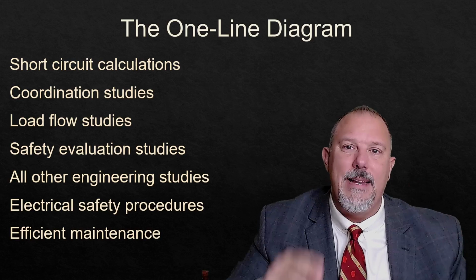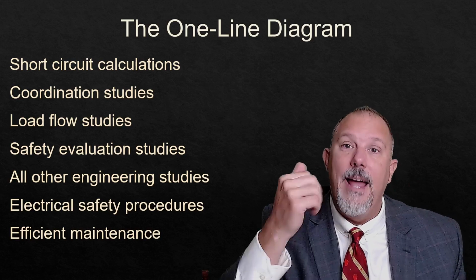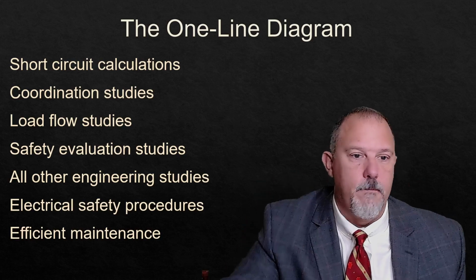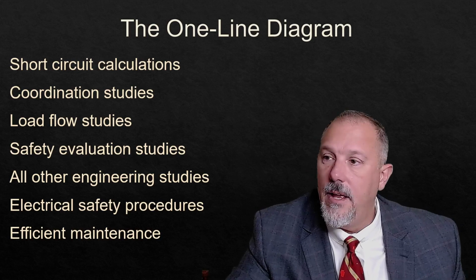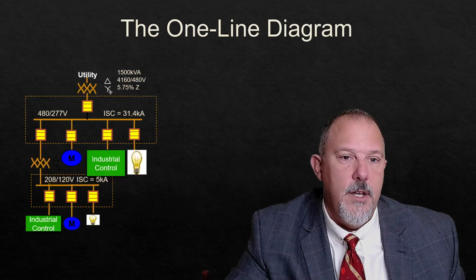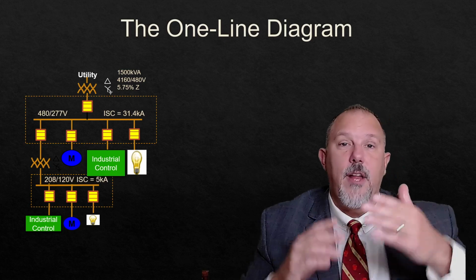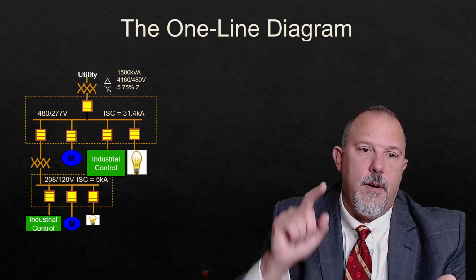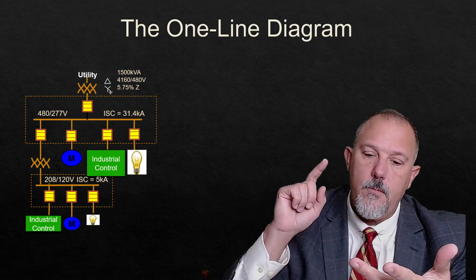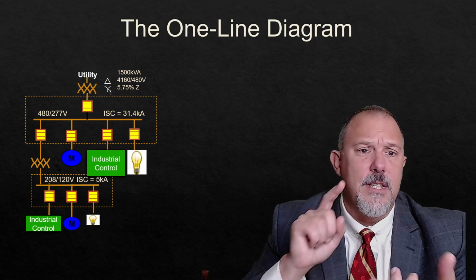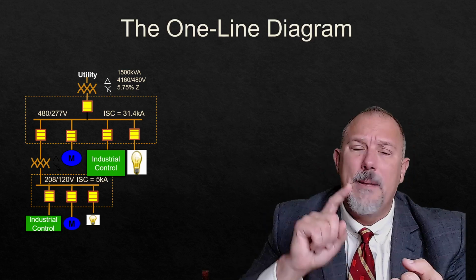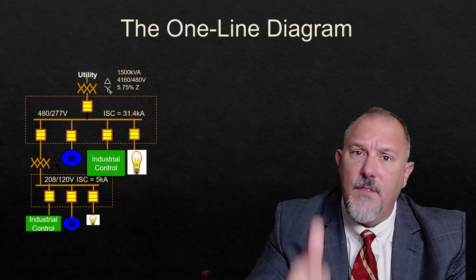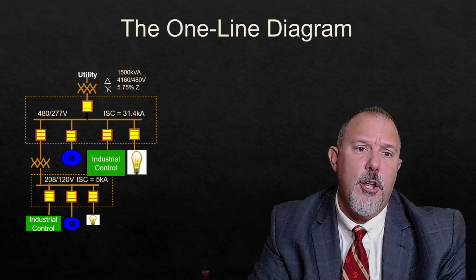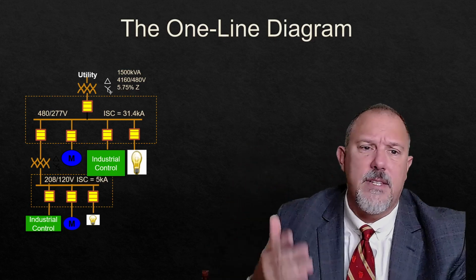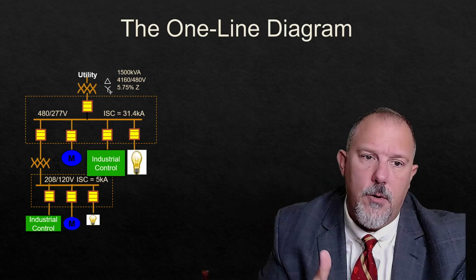Accurate, up-to-date, available. Three key things. Accurate, up-to-date, available. And efficient maintenance. It has all of the information you need. You should have the available fault current numbers on there. You need the length of conductors, the size of your transformers, the impedance of the transformers, kVA of the transformers. It'll tell you if it's a delta, Y grounded system, YY system. You need to know that information.